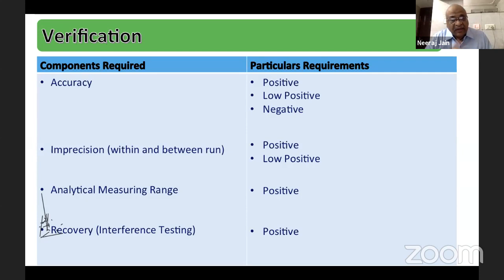And now suppose somebody else is saying, this machine is good, this method is good. You have to check about accuracy. You have to check about precision. You have to check for the analytical measurement range. And you also have to check about interferences. When you're buying a new equipment, you have to see so many things. First, see whether the space where you will put that machine is adequate or not, and what service backup you will get for that machine, the extent of technical training required, whether your people will be able to understand all those things or not, or some special training is required for them. Also see the instruction manual in terms of clarity and usefulness. If required, ask company people to elaborate on certain things.